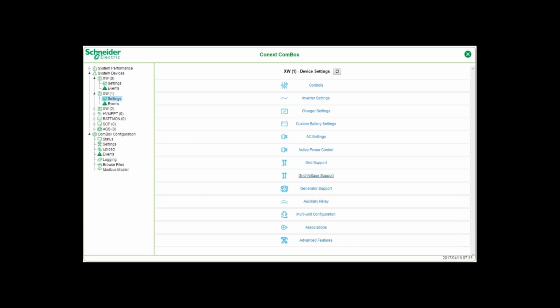Drilling down into the XW Plus settings menu, we see all the relevant settings applicable to system setup and control. So for example, controls would allow you to access inverter enable or disable, charger enable or disable, grid support, sell mode. Inverter settings would have low battery, high battery cutout settings. Charger settings would allow you to set up for battery type and capacity.